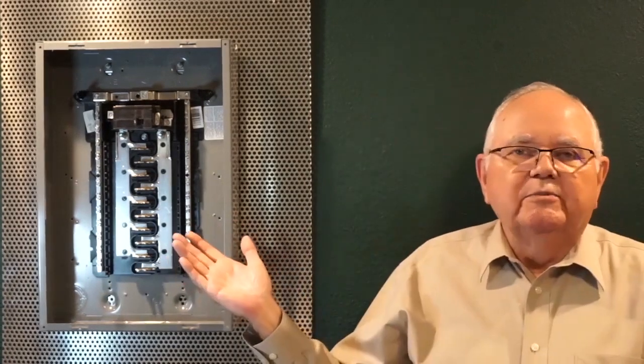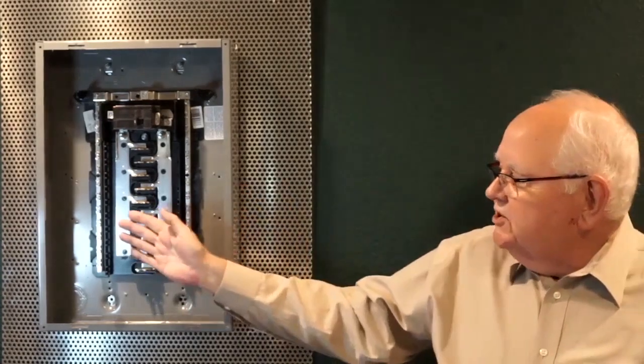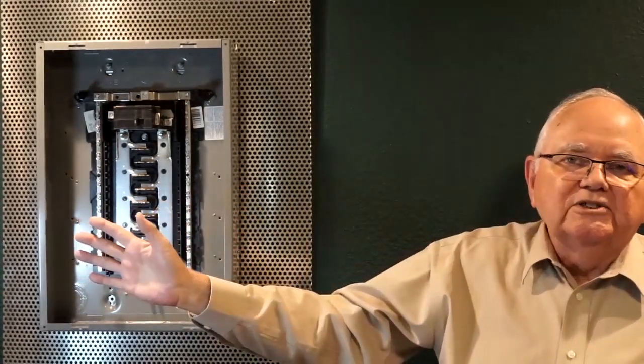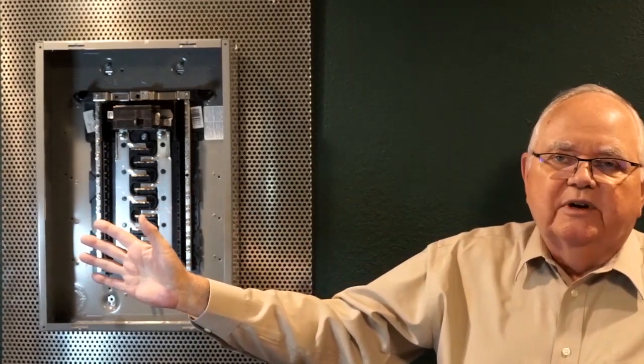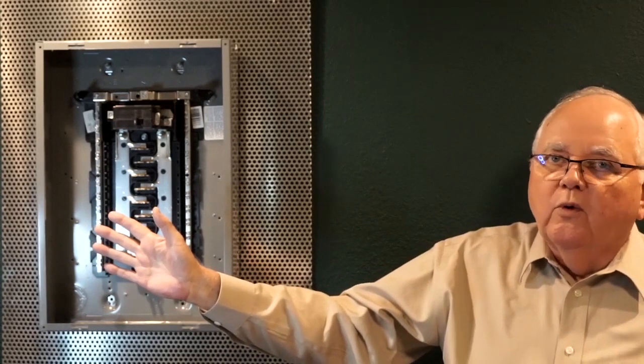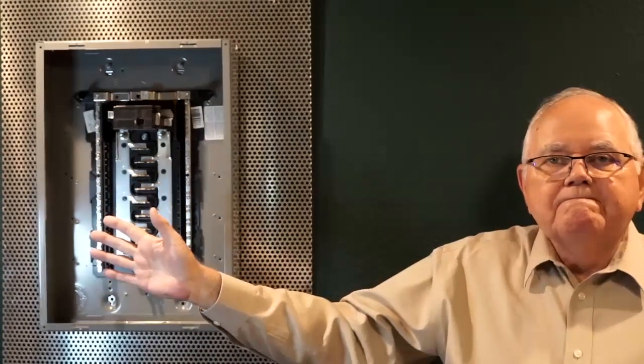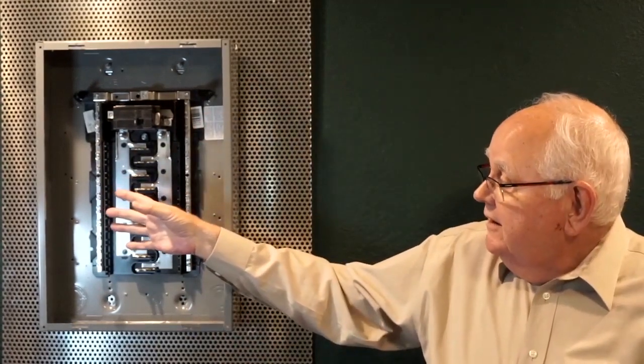So we do a shock risk assessment, the first thing. The next thing we're going to do is an arc flash risk assessment. That information, once again, is on the label. And it's going to give me the incident energy at a given working distance. So let's say that the most typical working distance on a panel board like this is going to be 18 inches. So our engineers do a calculation and they say that 18 inches away from that arc flash, I would be hit with so many calories per square centimeter, whatever it is, 2 calories, 2.4, 1.7, 4.8, whatever it is. Okay. I need to make sure that my skin is protected so that I don't get any burn injuries. So I must select some PPE that's going to equal or at least equal, if not exceed, that calorie rating then, right?